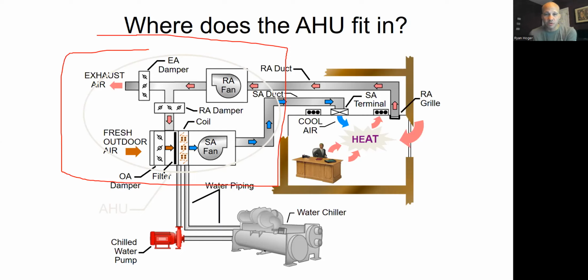Right, we talked about this before. This is the device that moves air around the building. So we've got supply fans, sometimes return fans, ventilation dampers, exhaust dampers, filtration, and then most importantly for today's discussion, we have the cooling coil, and you're probably going to have a heating coil as well, right? So that cooling coil is going to be an indicator to me if it's a chilled water system and being fed by cold water. Typically 44-degree water goes out to the coils. 56-degree water comes back, historically speaking. Not every job's that way.